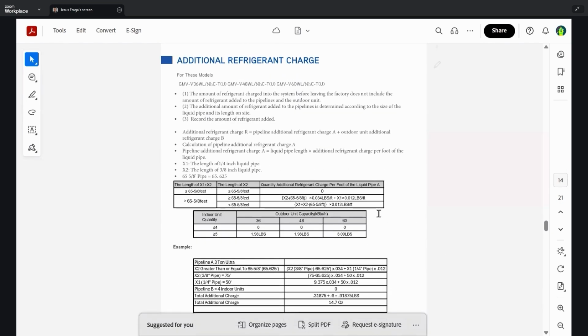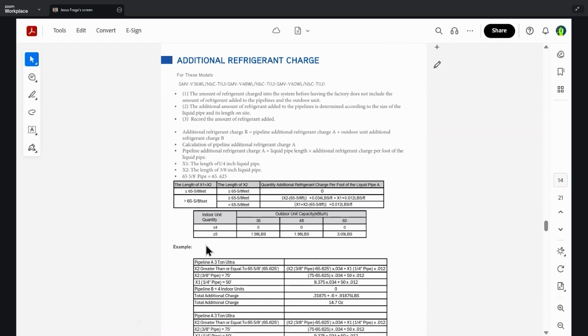This is an example of additional refrigerant, and we've provided a couple different examples here for you, so you're able to decipher how to calculate the additional charge. This applies to the GMV V36, the 48, and the 60. As I stated, there's a couple examples here that you can follow and ensure that you have the correct additional refrigerant whenever it comes to that point in the installation and startup process.